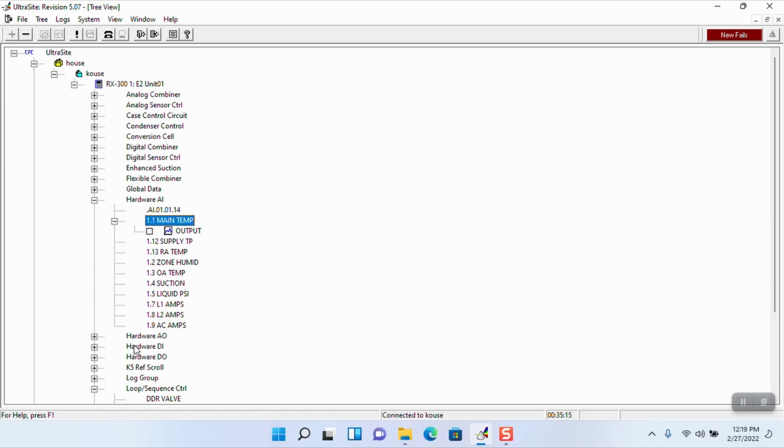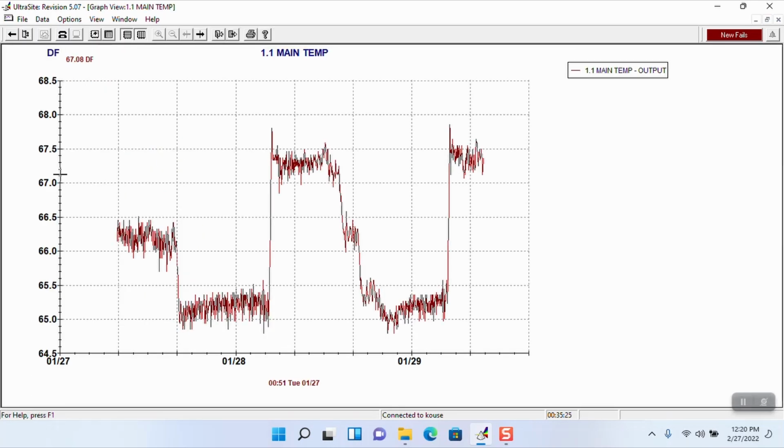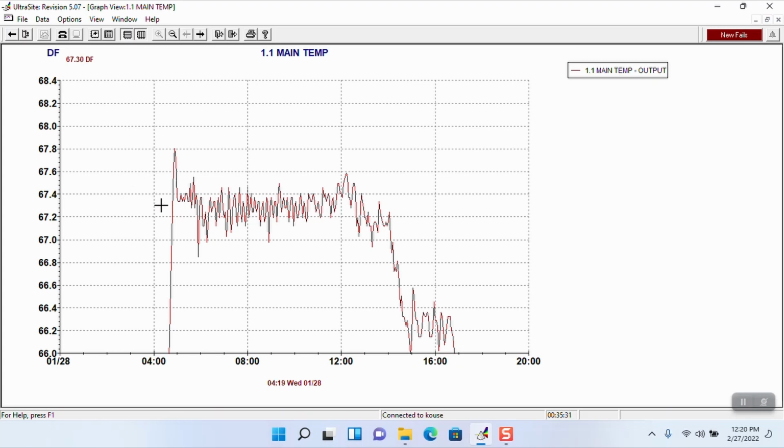So we'll do this. Generally, when you graph these, you'll have a set point through it. You'll have two lines. You'll be graphing set point, so it'll have a set point shot through the center, and then we'll say, for example, our set point is 67 degrees. So at 67 degrees, we'll have a line shot through the center right here. Then we should be following that line. You can see this thing's overshooting. So she has it set for 67.